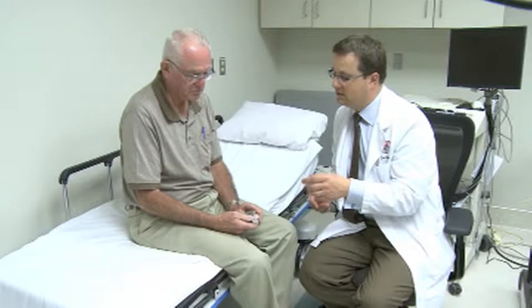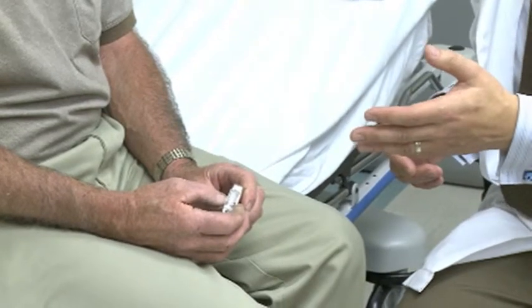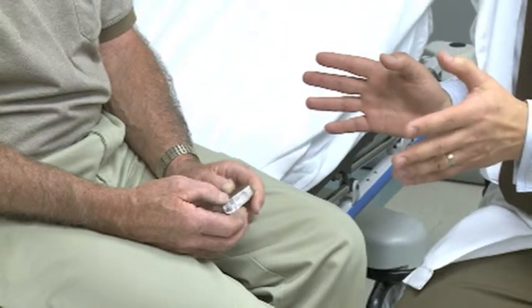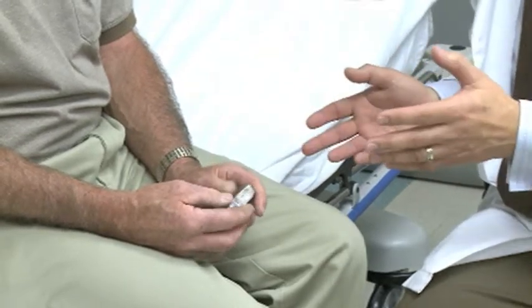If it sees too many heartbeats, it watches for a little while and then tries to figure out, is it a heart rhythm problem that could be, you know, life-threatening or not? Make some measurements, and after about automatically charge up and give a shock to the heart to reset it. Or it might just sit there and watch for a bit longer because it thinks that the signals aren't real signals. So let's say you were...